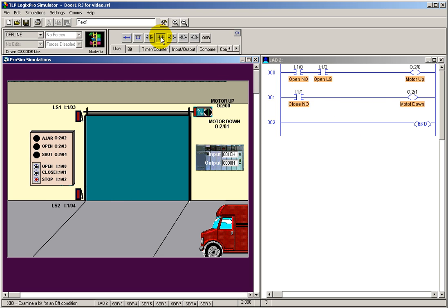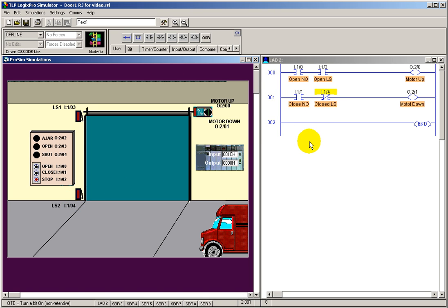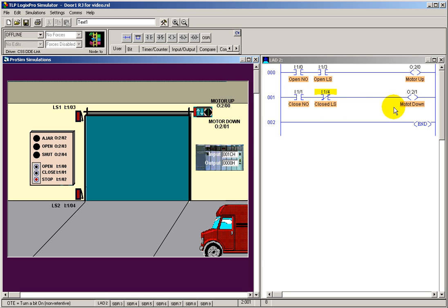This one's the opposite. We're going to grab an examine if open and drag our address from it. This is a closed limit switch. Remember, the limit switches physically are the same, but the way we're going to handle them is completely different. This is examine if open. If it's open, we'll allow this close button to energize the motor down.